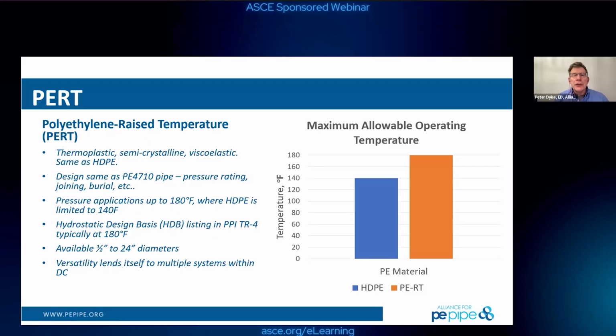One more question for you: you refer to polyethylene as 4710—what does that mean? That's the grade of HDPE we use today. Each letter or number has a meaning. Within the standardization system, ASTM D3350, the 4 means it's high density, the 7 means extremely high slow crack growth resistance, and the 10 is the stress rating of the material in units of 100 psi—so essentially a 1,000 psi long-term hoop stress rating. That's what all the standards today require for municipal piping applications and industrial piping, FM certified material, firewater systems—they all use PE 4710 grade materials today, and they're readily available. It's the highest performing, really the 4th generation of pressure piping materials for polyethylene.